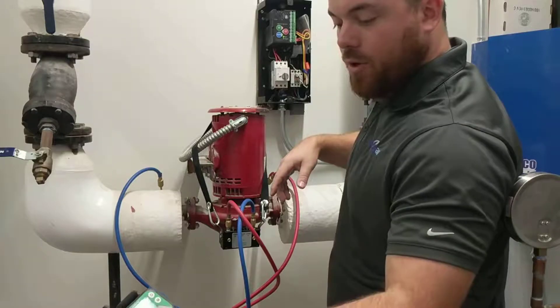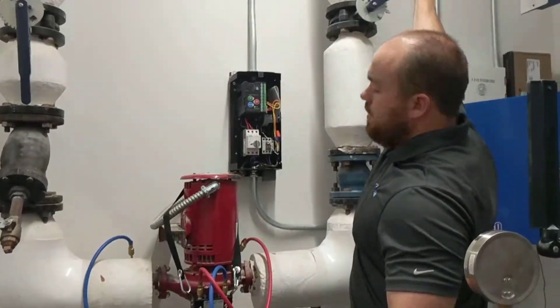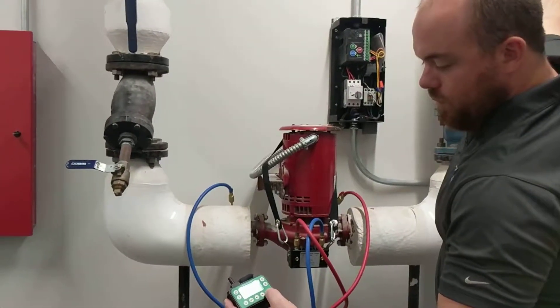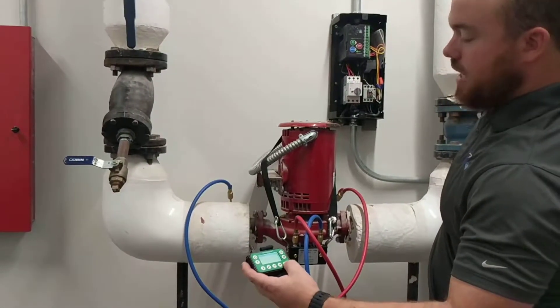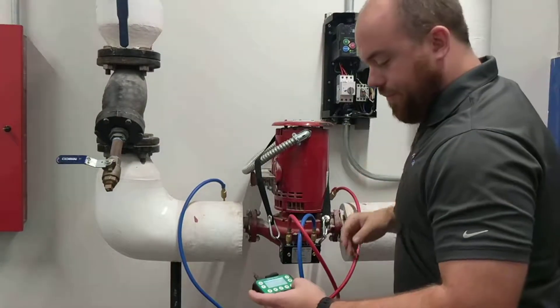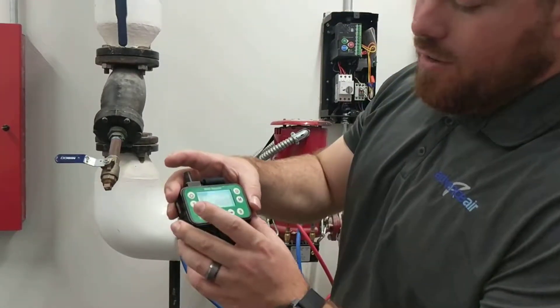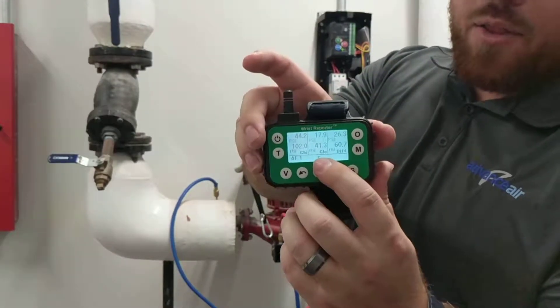We'll deadhead the pump and I'll show you how that works. We'll deadhead the pump, then hit the S button to save. We'll open the pump back up. You can see here that this is a live shot, but if we scroll over, you can see reading number one — we're at 60 foot head on the pump.